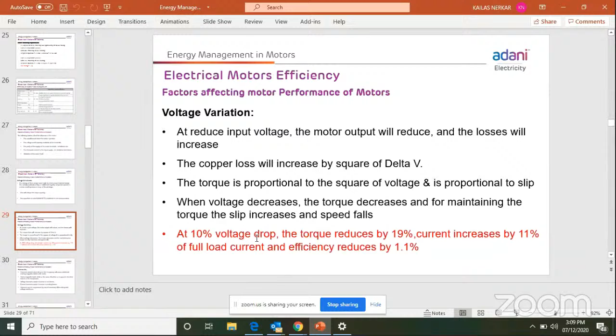Now the factors affecting motor performance, you can see the voltage variations. If the input voltage is reduced, the motor output will reduce and losses will increase. The copper losses will increase by the square of delta V. That means voltage variation matters.